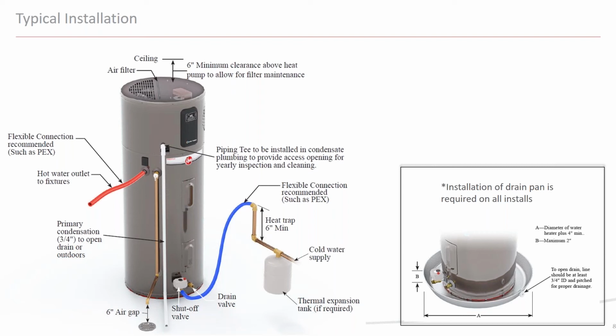If you're installing this in the basement or central part of the house where there's no drain accessible, you can always get a 2 gallon per day condensation pump and pump it to where there is a drain. It's a bit more installation work, but obviously you don't want 2 quarts of water hitting the floor of a homeowner's home every single day. So there are ways to get around not having a drain source right next to the water heater.